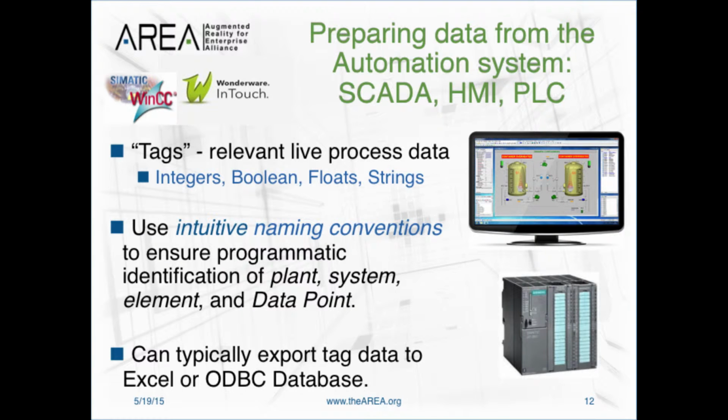So basically, it is possible, since we know the PLC and we know the SCADA system and we know the point that that tag is relevant to, if they have used some type of same naming convention for the PLC, for the connection, then I can identify that point all the way down. And typically, these types of software systems have a way to export this out into Excel, which gives us a gateway into a database, and then we can use it. So typically I'll talk to the engineers, I'll look at, hopefully they've used some type of naming convention, we might have to do some mapping.